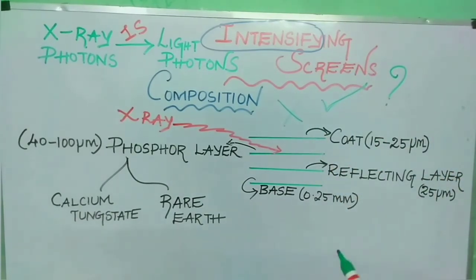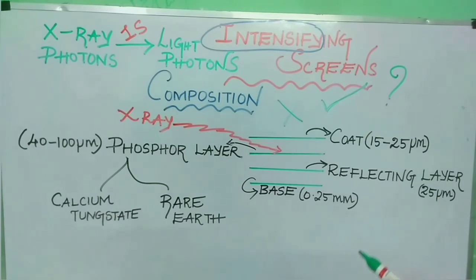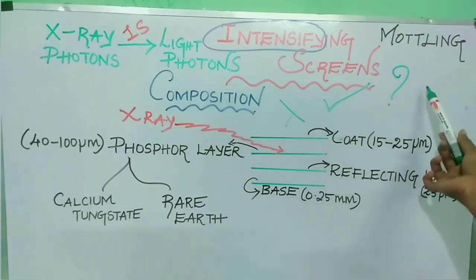The major disadvantage of using an intensifying screen is that it produces images with less resolution. This is because of the gap present between the intensifying screen and the film and also because of the diverging light photons emitted in all directions. Another disadvantage is that it produces mottling, which is an irregular pattern of density. This occurs because of non-uniformity in the coating of fluorescent phosphor crystals.